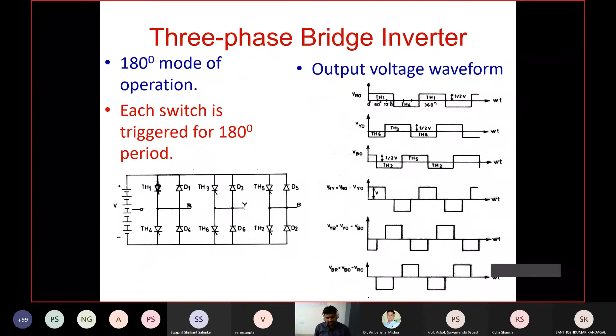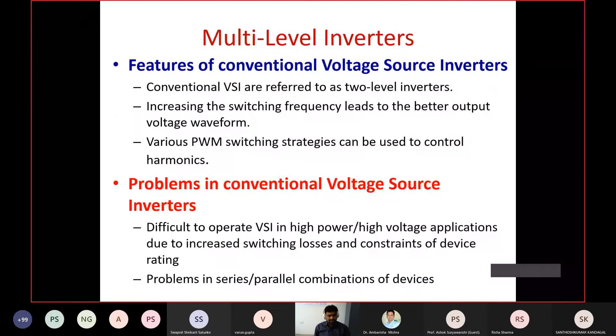But when integrating with a grid system, the AC side output voltage may require about 11 kV or more. In such cases, the DC link voltage you'd need to inject into the inverter becomes very high, and a two-level inverter cannot sustain that. That is the first reason why we go for a multi-level inverter.